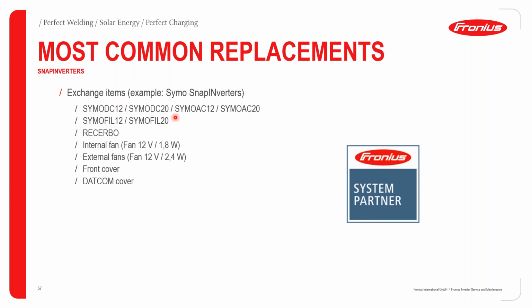Also, your filter boards could be something else to look at. The receiver board, which is the display board, is connected to the data manager, and it could get blown if you have not adequately protected your comms against lightning surges. Also your internal fans and external fans - it could happen that you need to replace them. Also your front cover and your DATCOM cover.